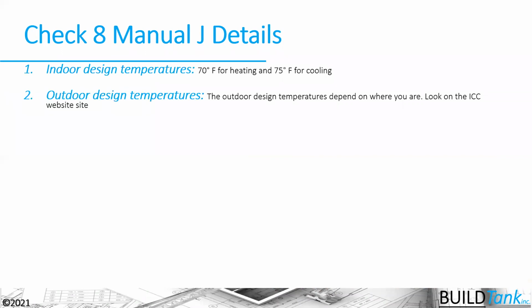And there are eight things that we need to look at on the Manual J to guard against any manipulation that the HVAC contractor might be doing because they don't have confidence in that thermal envelope. We need to look at the indoor design temperatures. We need to look at the exterior design temperatures. This creates the delta T, or temperature difference across our assembly, that is the biggest driver for the heat loss or heat gain in that house.